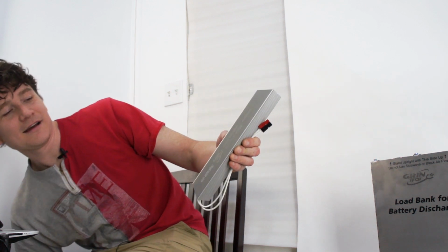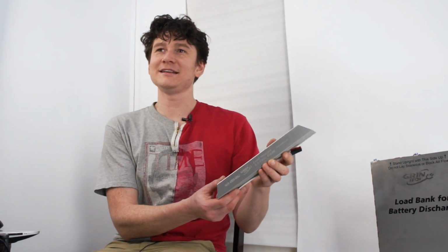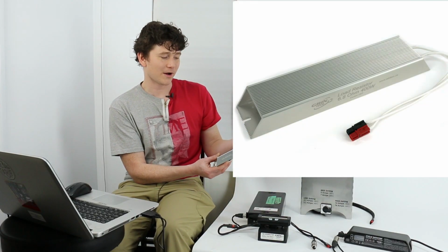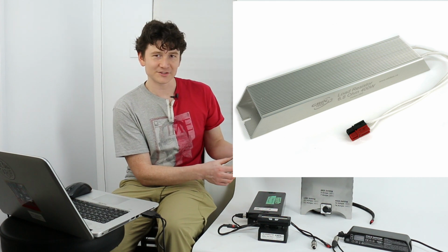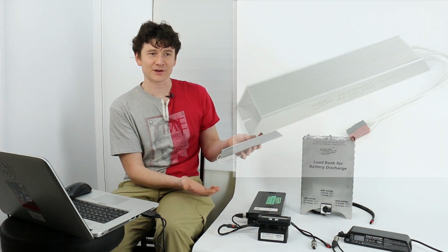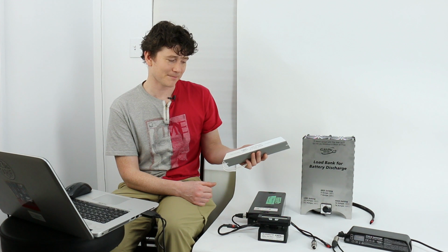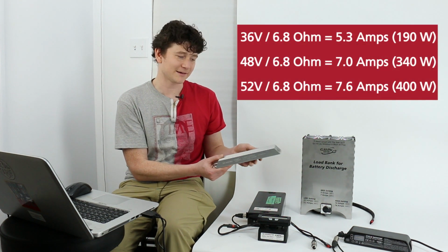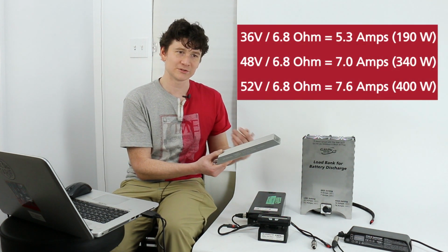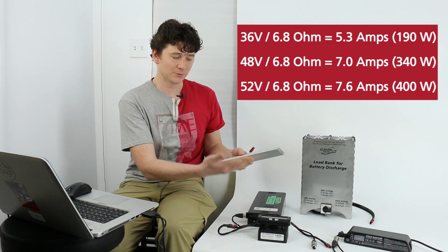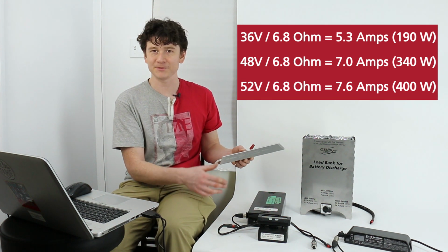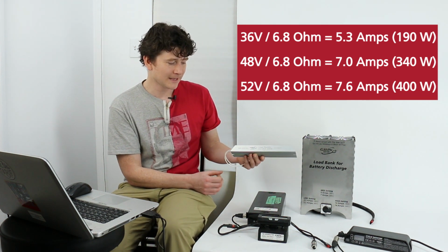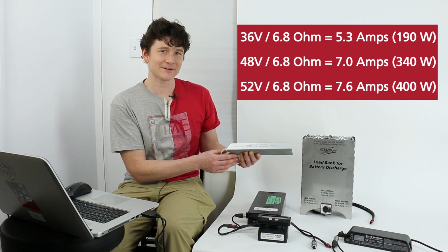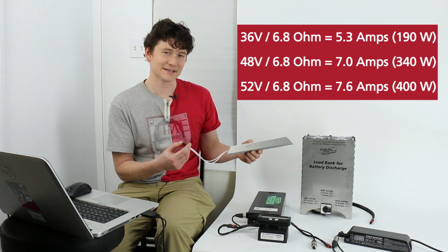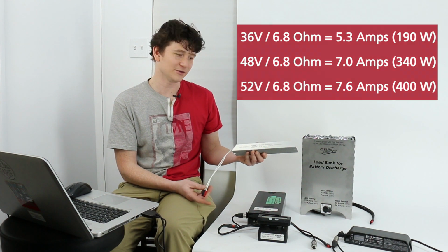Our preference is these extruded aluminum load banks, battery loads, and we stock these in a 6.8 ohm, 400 watt model. We chose this 6.8 ohm resistance because it's very convenient for the current levels you'd want when testing an e-bike battery. With a 36 volt battery, one 6.8 ohm load results in a 5 amp discharge. Put two in parallel and you get 10 amps; four in parallel gives 20 amps. With a 48 volt pack, you get 7.5 amps per load, and with a 52 volt pack, it's closer to 8 amps.